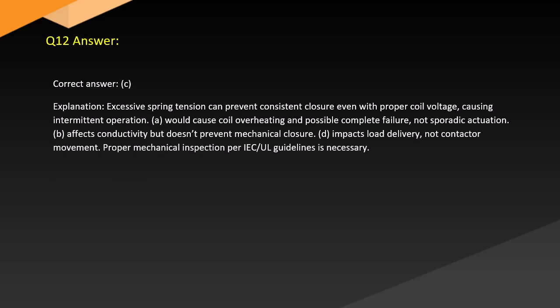Answer. Correct answer: C. Explanation. Excessive spring tension can prevent consistent closure even with proper coil voltage, causing intermittent operation. A. Would cause coil overheating and possible complete failure, not sporadic actuation. B. Affects conductivity but doesn't prevent mechanical closure. D. Impacts load delivery, not contactor movement. Proper mechanical inspection per IEC/UL guidelines is necessary.